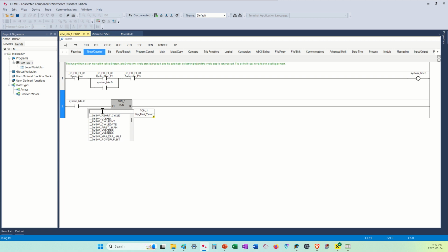If I know exactly how much time I want that timer to be, I'm going to take the letter T, and then I'm going to put a hashtag. So it's not like they do on the internet where a hashtag will help you jump to something. This is to delineate that the T is a time data type. Then I simply need to type in the minutes, seconds, hours that I wish.